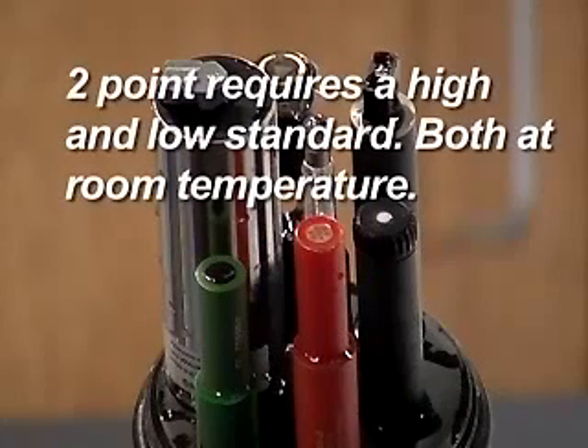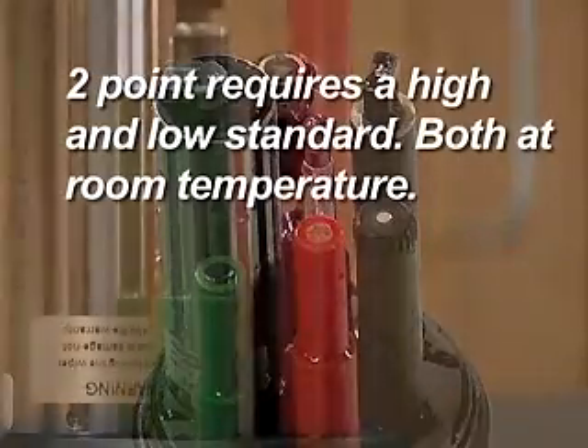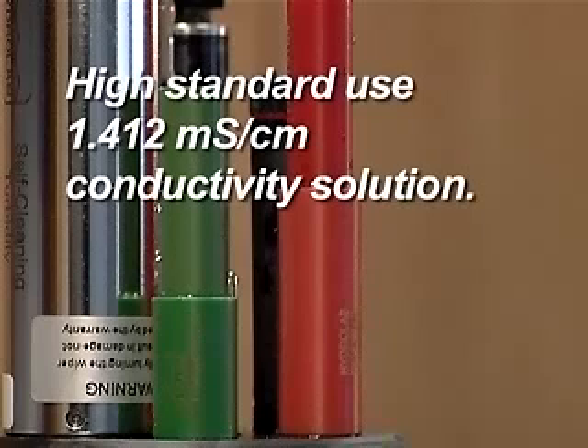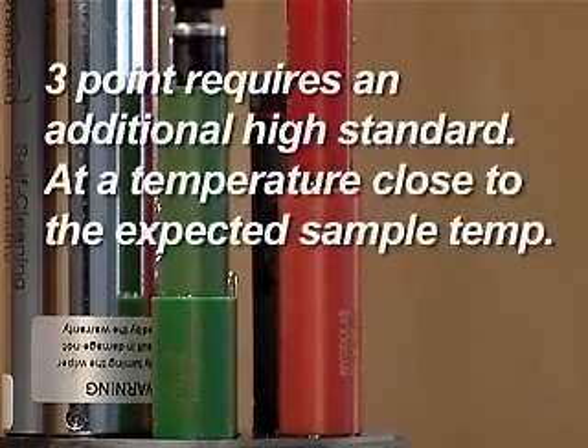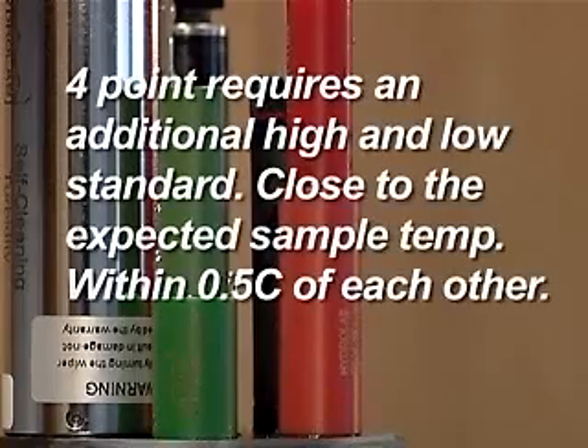A 2-point calibration requires a high and low standard, both at room temperature. For the high standard, use a 1.413 millisiemens per centimeter conductivity solution. A 3-point calibration requires an additional high standard at a temperature close to the expected sample temperature. A 4-point calibration requires an additional high and low standard close to the expected sample temperature and within 0.5 degrees centigrade of each other.